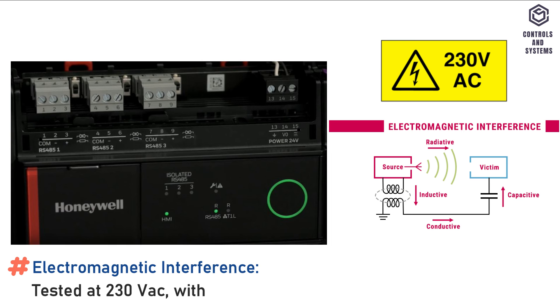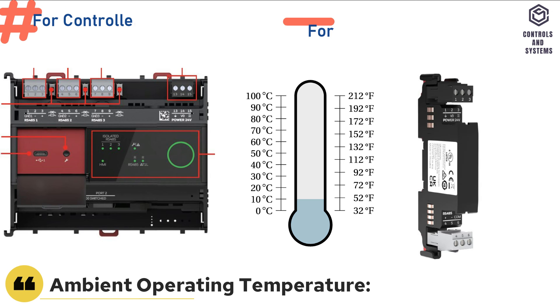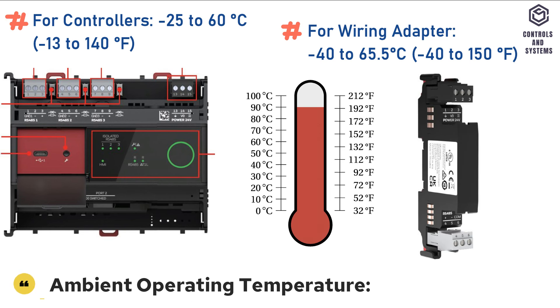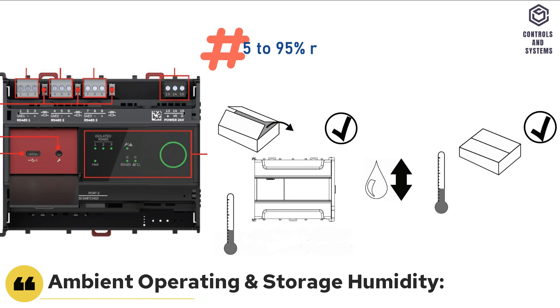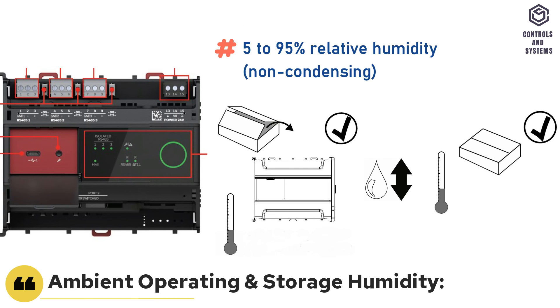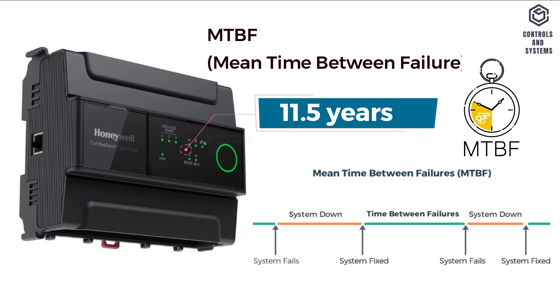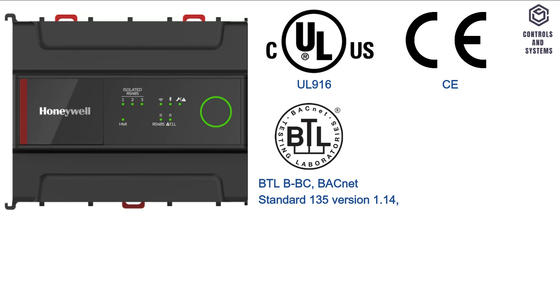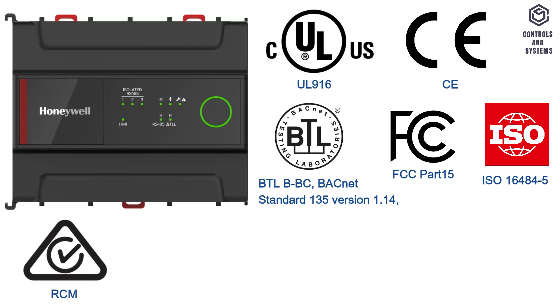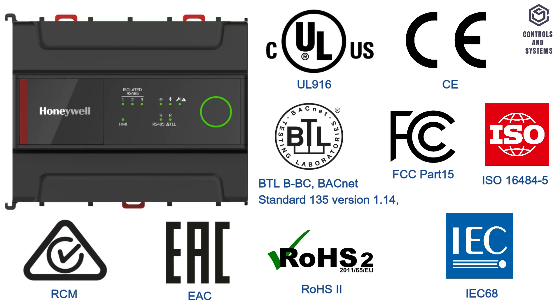Electromagnetic Interference tested at 230 Volt AC with modules in normal condition. Operating Environment: Ambient Operating Temperature for controllers is −25 to 60°C; Storage Temperature is −28.9 to +70°C. Ambient Operating and Storage Humidity is 5 to 95% relative humidity non-condensing. Vibration under operation is 0.024 double amplitude. Mean time between failure is 11.5 years. Certifications: Underwriter Laboratories 916, Conformité Européenne, BACnet Testing Laboratories, Federal Communications Commission, Regulatory Compliance Mark, Eurasian Conformity, Restriction of Hazardous Substances 2. Testing Electrical Components: IEC 68.